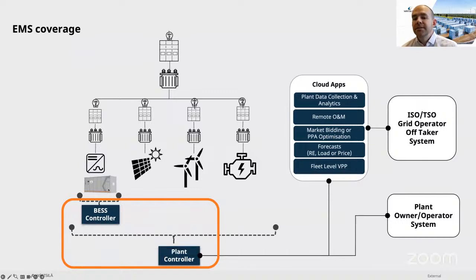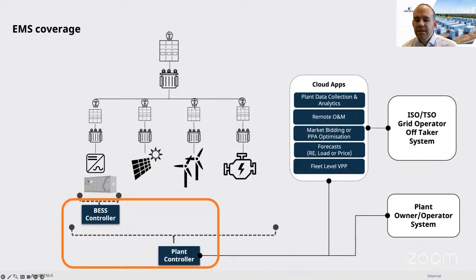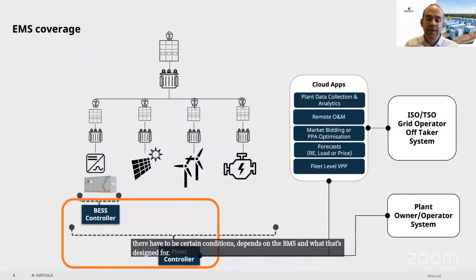The part that gets a little tricky in these modern massive utility scale plants is that there have to be certain conditions, depending on the BMS and what it's designed for, to then trigger the balancing. So it often doesn't just happen all on its own all the time. Unlike active continuous balancing, often you have to have the SOC at some level for a certain period of time to trigger that balancing.